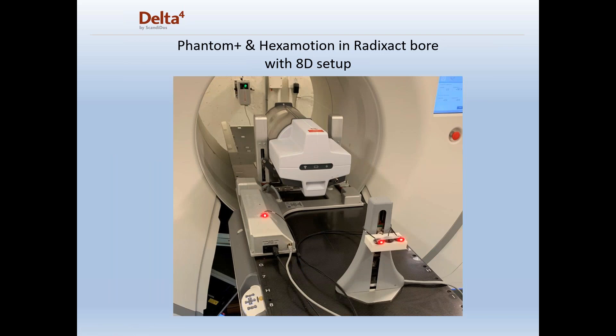This is a setup within Accuray's Radixact system. What sets the Delta4 product apart from anything else in the market is that we can do up to 8D setup for the Synchrony software on Radixact. That allows six degrees of motion for the Phantom Plus on the HexaMotion system, plus an additional stage that allows you to track breathing motion. The two dots on the platform go up and down to represent the chest wall or abdomen of the patient moving during normal breathing during treatment.